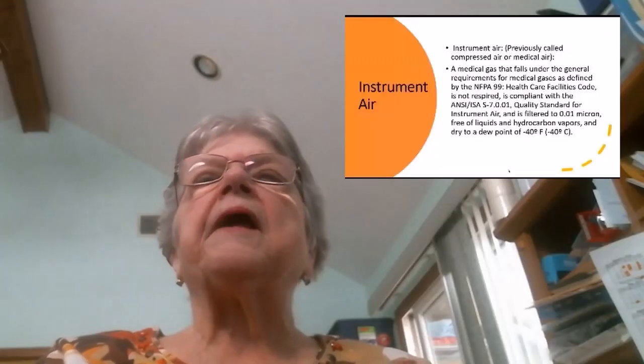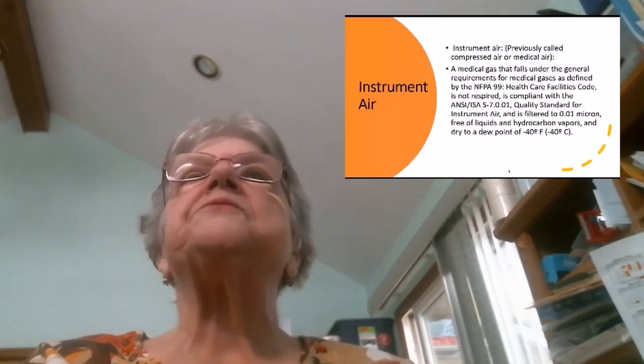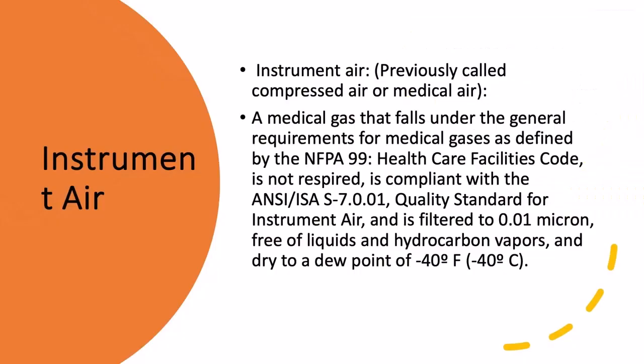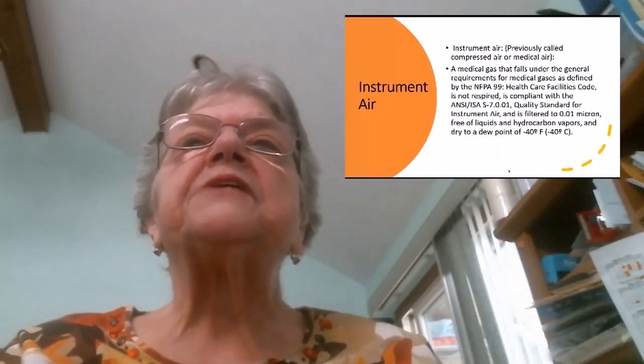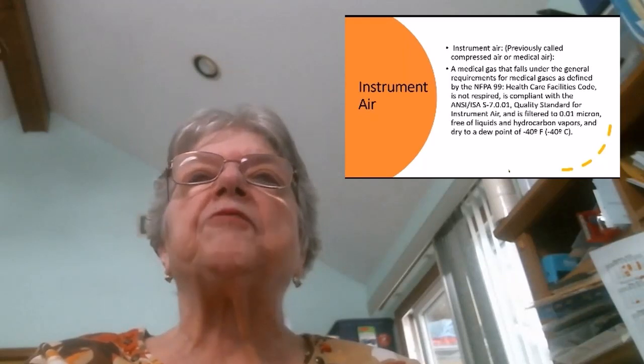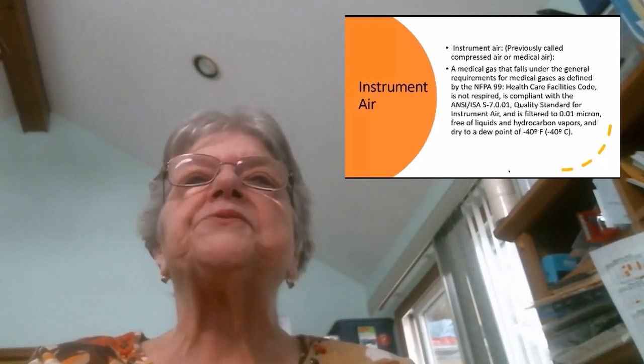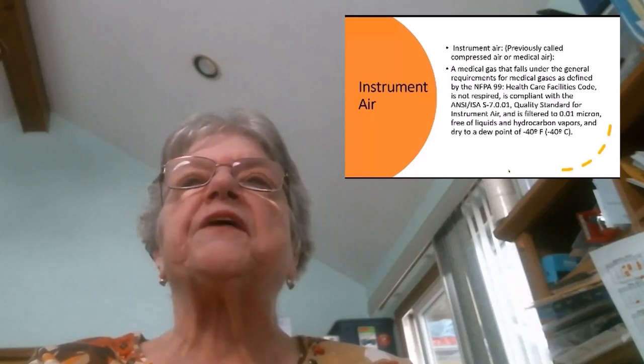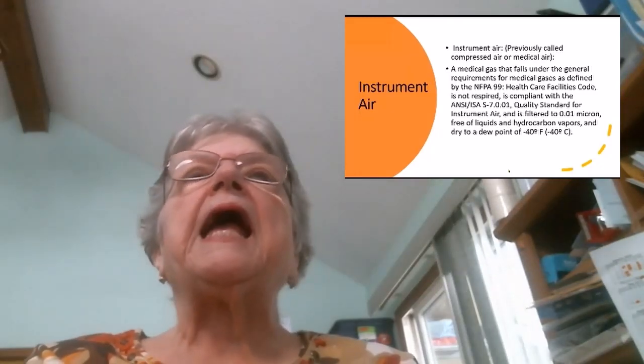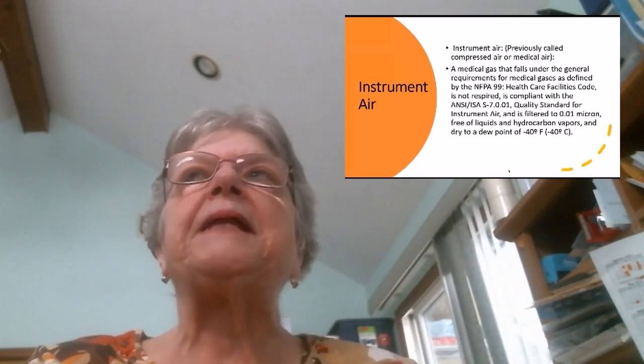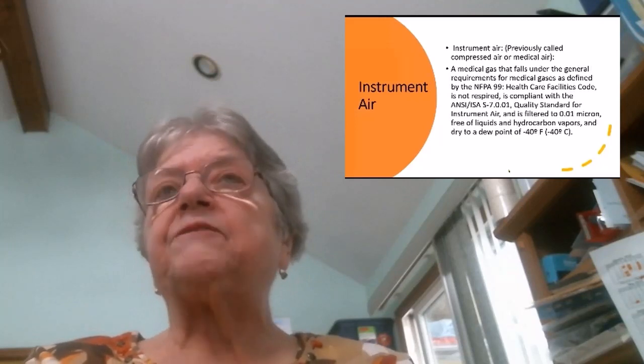Now, we mentioned instrument air. A lot of people are not familiar with it. For years, we used compressed or medical air, and we found out when we were updating ST79 that that's in violation of fire code. So instrument air is a medical gas that falls under the general requirement for medical gases as defined by National Fire Protection Association 99 Healthcare Facilities Code, and is compliant with the ANSI quality standard for instrument air. And the reason it's different is instrument air is filtered to 0.01 microns, is free of liquids and hydrocarbon vapors, and dry to a dew point of minus 40 degrees Fahrenheit. This is very, very pure air. And the reason it's recommended is we don't want to recontaminate our scopes or any lumens after we've cleaned them.